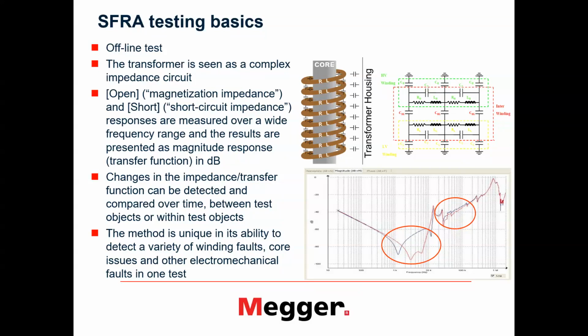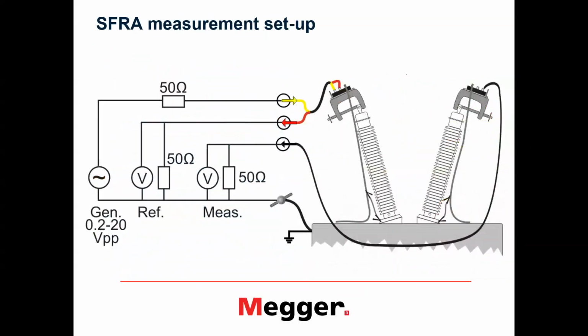This method is quite unique, and it is able to detect quite a few winding faults, core faults, and other electromechanical issues in a transformer. It may sound like a very complex test, but actually the test setup and the measurement hardware are pretty simple. You have a generator.